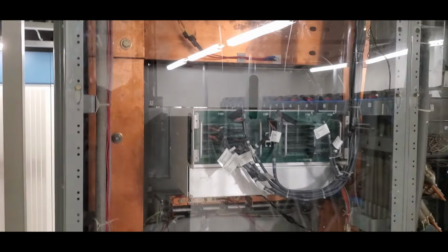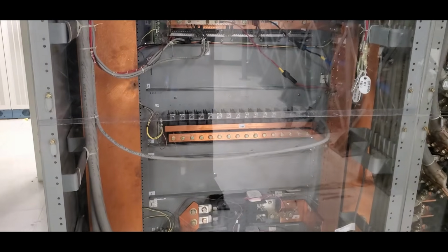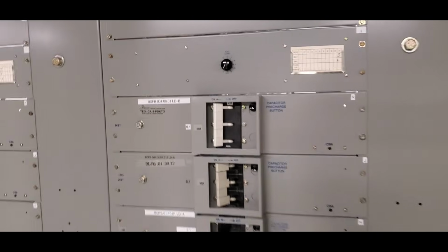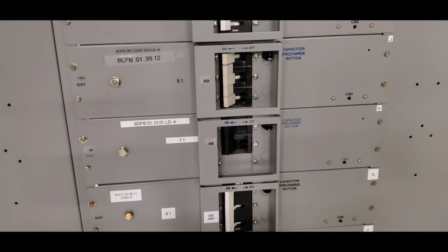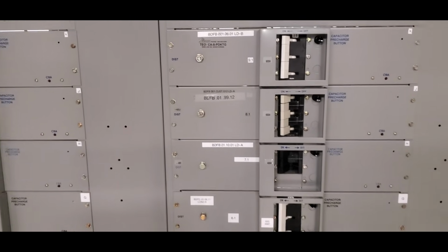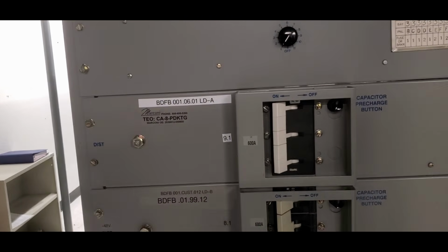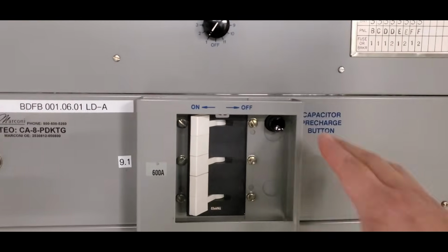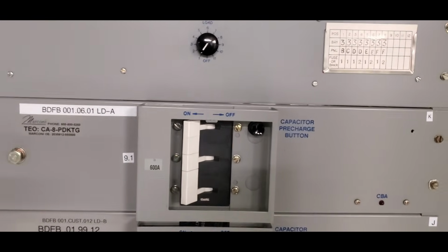Here is the back of that controller, so that's the controller itself. And then you see all the copper, that's all the buses. And then down there are the circuit breakers. And these are the various circuit breakers for the DC side of things. Now these themselves don't produce power for the equipment. What these do is send power to the breaker distribution fuse boards that we'll show you in a second also.